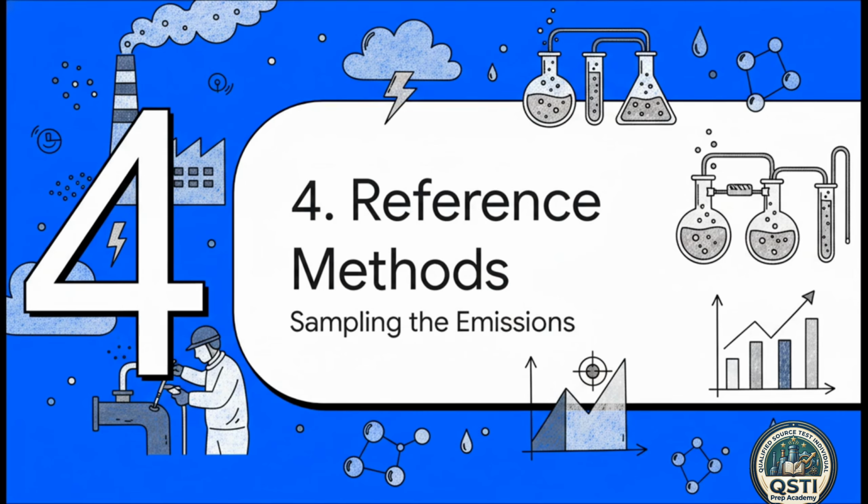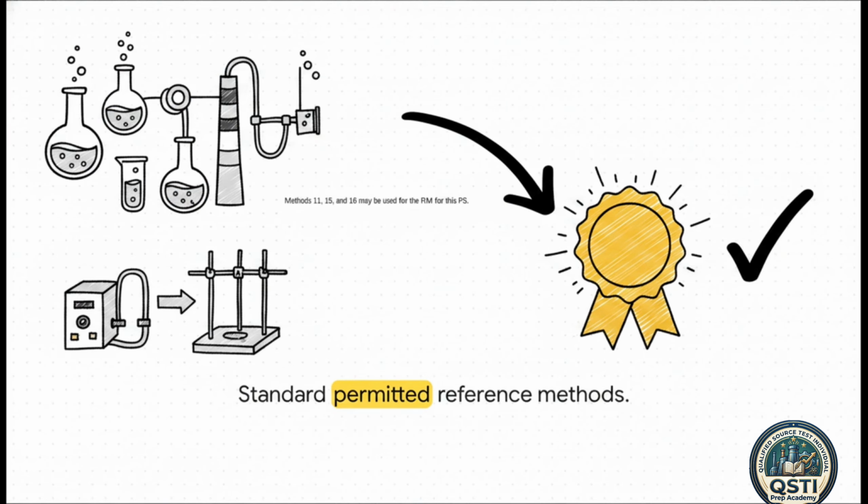Which brings us to Section 4, Reference Methods and Sampling. Time to cross-check that data. Now, what's really interesting about this is how the EPA handles the sampling strategy. Unless it's otherwise specified in a totally different subpart of the regulation, Methods 11, 15, and 16 are your standard, permitted reference methods for this performance spec. These are the absolute gold standard manual sampling methods that you must use to cross-check your automated system.